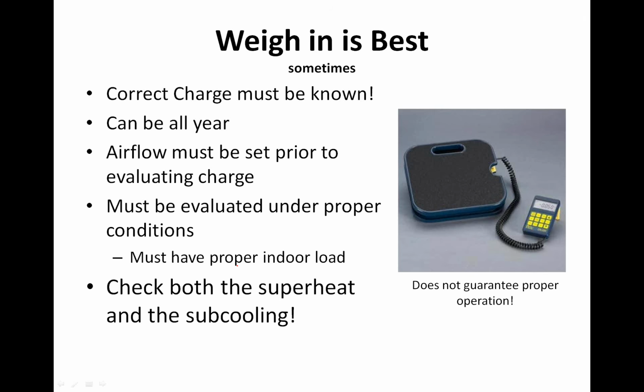And the airflow, though, before we can evaluate it, we've got to get the airflow set, and it's got to be evaluated under proper conditions, because weighing in the charge doesn't guarantee proper operation. The TXV could be installed incorrectly, or you may have a restriction in a line set, or it may be a kinked line or another issue in there. You've still got to go back and commission the system.